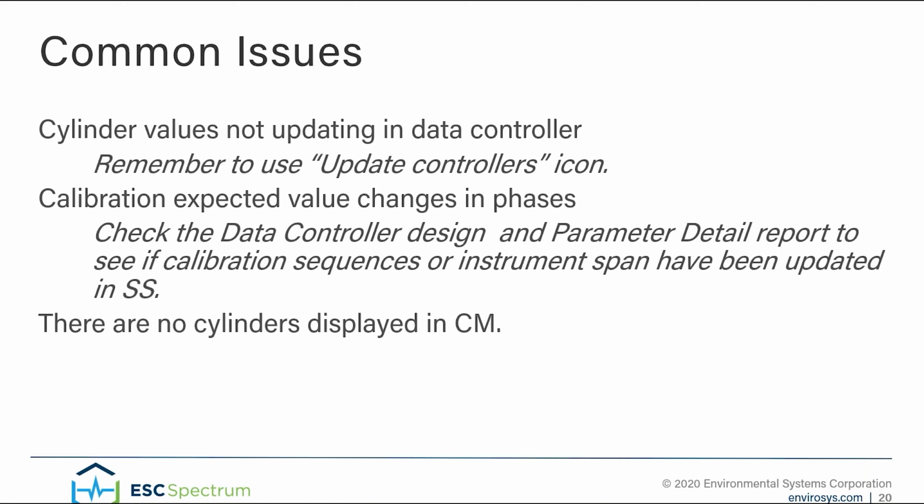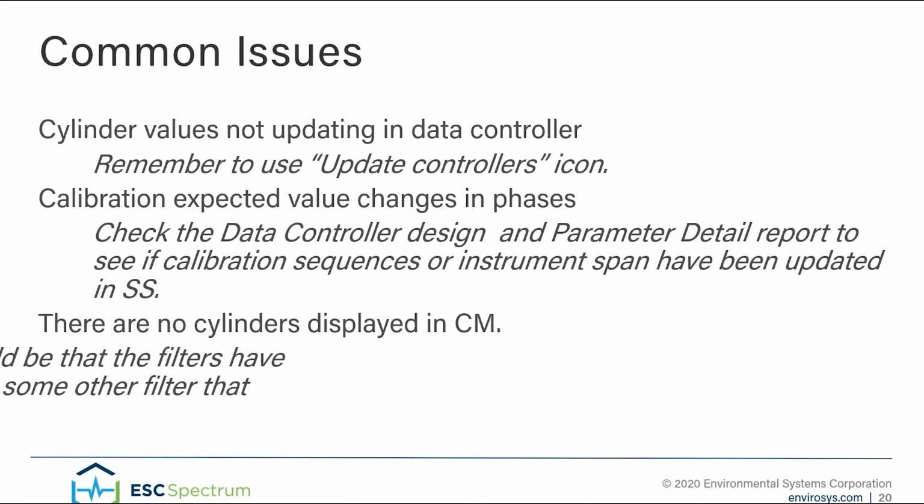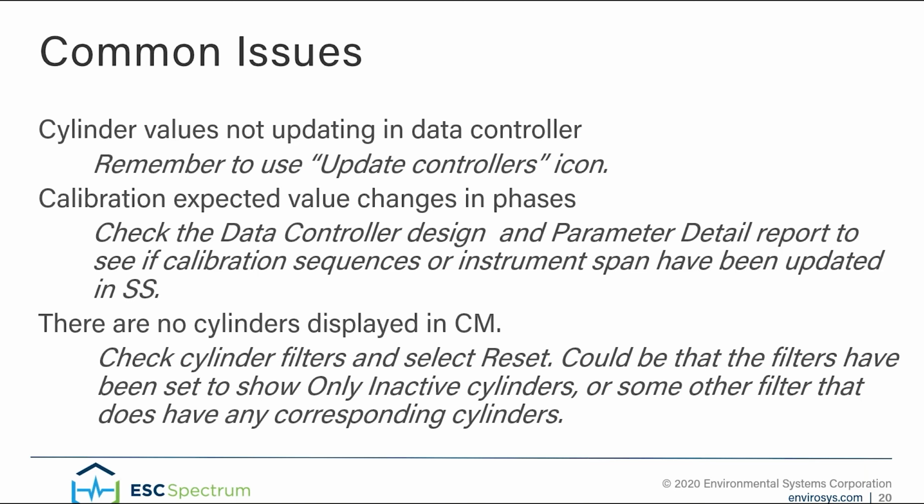There are no cylinders displayed in the cylinder management tool. That's a simple fix. Check the cylinder filters and select reset. Could be the filters have been set to show only inactive cylinders or some other filter that does not have any corresponding cylinders. So again, if I say only show inactive cylinders, I don't have anything to show me, so I'll have a blank page.